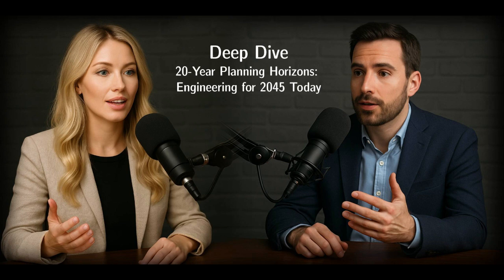So for a new data center substation, maybe phase one gets you a 230 kilovolt to 69 kilovolt, 300 megavolt-ampere transformer, 4 circuit positions, just what you need now. But the site layout, the foundations, the control house, they're all designed so phases 2 and 3 can easily add more transformers, maybe upgrade the voltage to 500 kilovolt, get you to 1,000 megavolt-ampere capacity as the demand actually materializes. No major teardown needed. So build the bones for the future, but only flesh it out when needed.